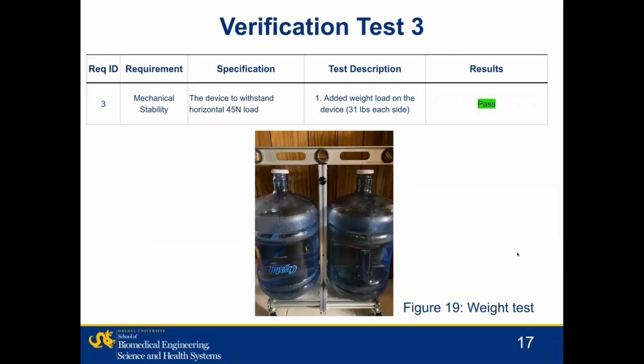So for verification test 3, this was done to test the mechanical stability of our new base design. So in figure 19, you can see where we added 31 pounds to each side of the device to ensure that it could meet the specification of withstanding a horizontal load of 45 newtons. And we concluded that this new base design passed this verification test.